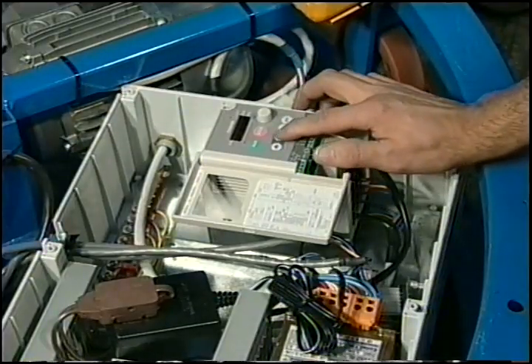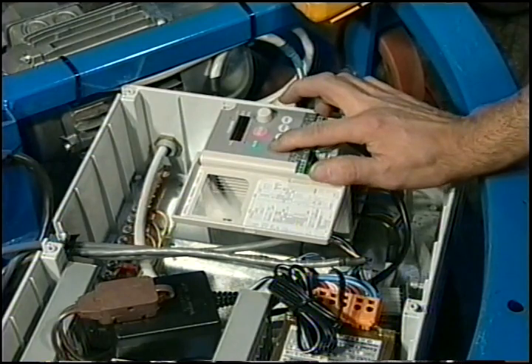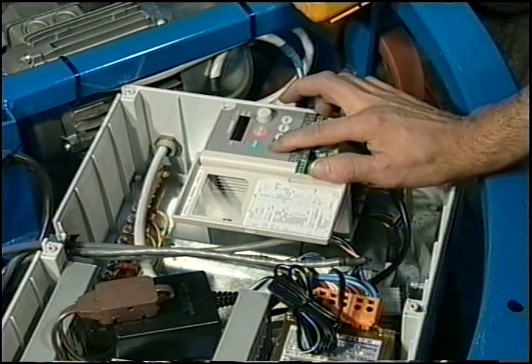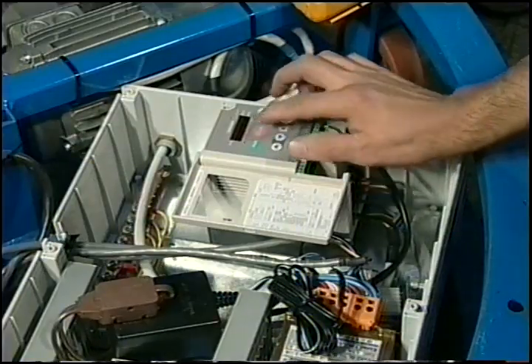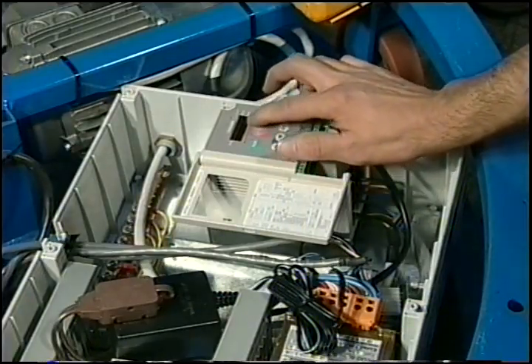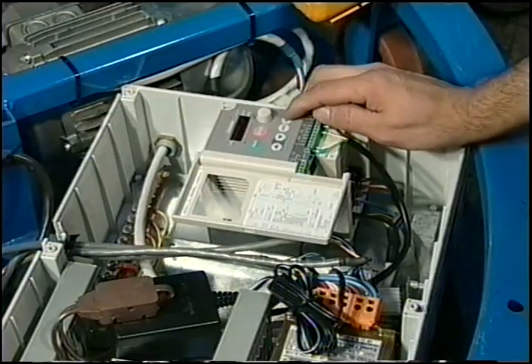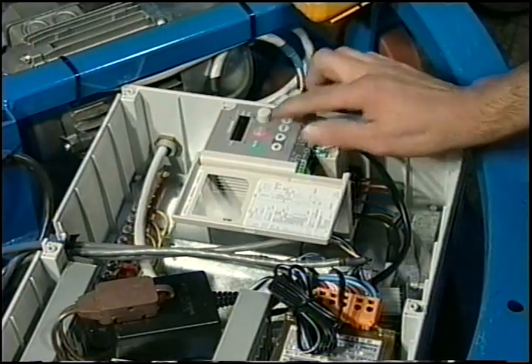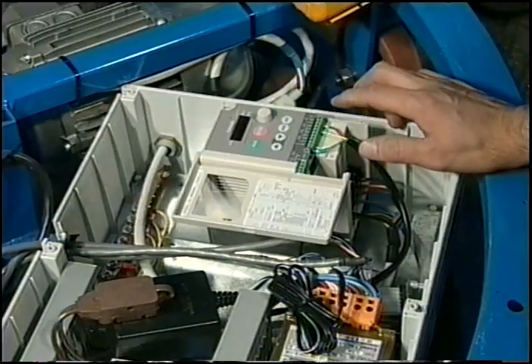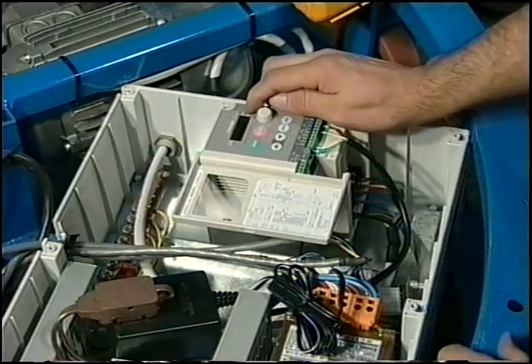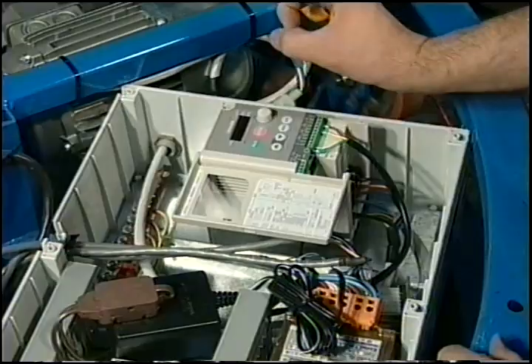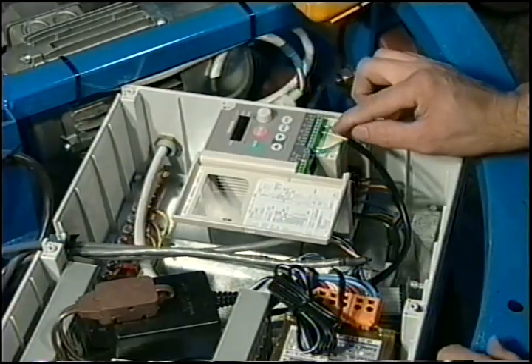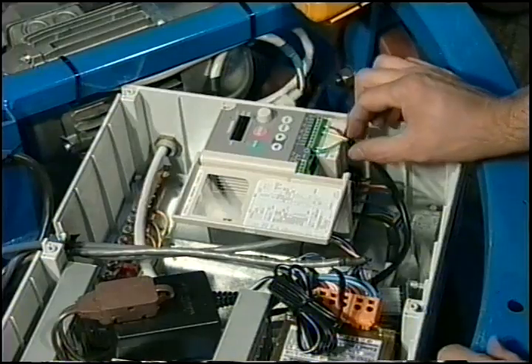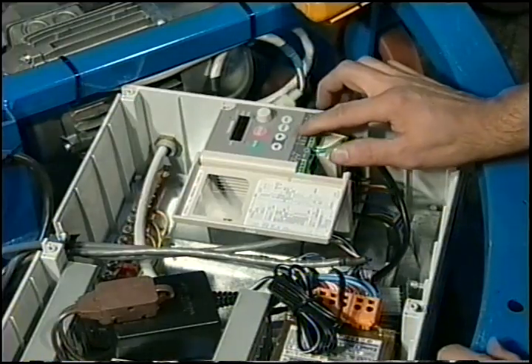The one I want to go into: if you hit the up arrow button, it'll progress through all the different parameters, and then you're going to see a command that says CNOD. At CNOD, if you hit the enter button, it's going to show you the value of that parameter. Currently it's set at 1, but on normal conditions it would be on 0. 0 means that it's going to look for a peripheral device, which is here, to tell it what to do.